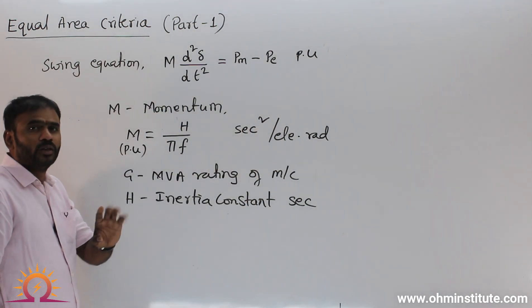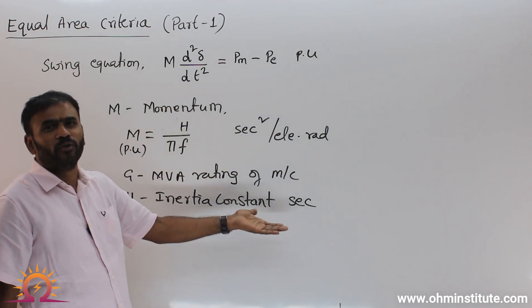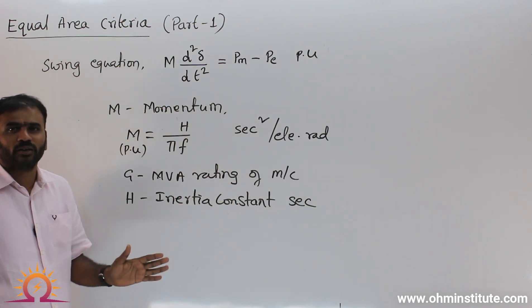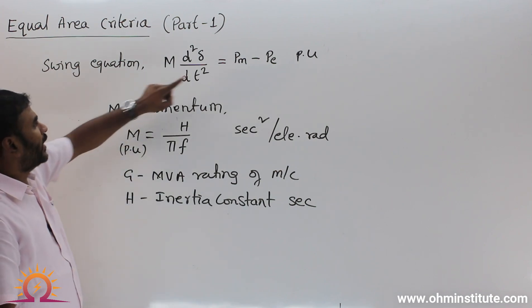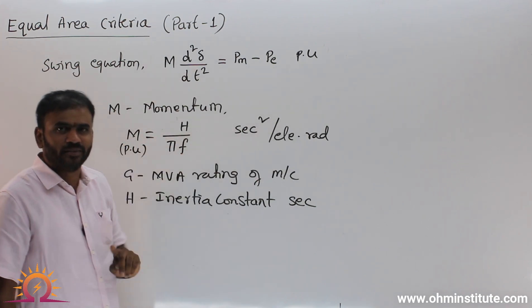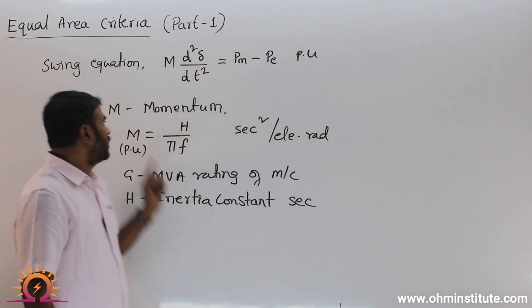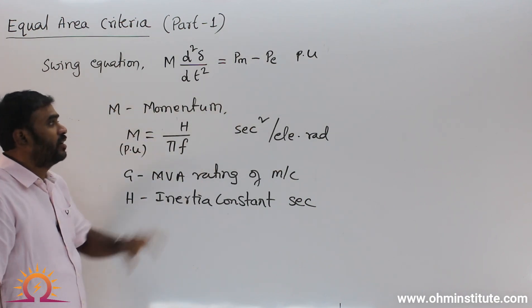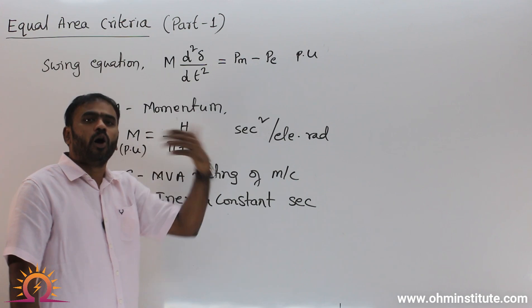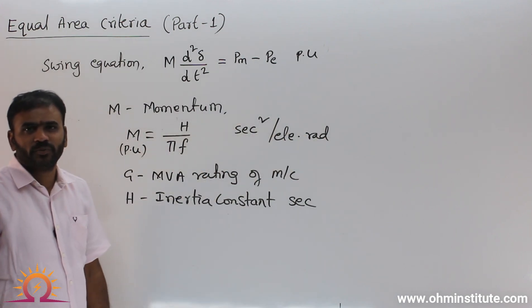In per unit form, the units of M become seconds squared per electrical radian — not mega joule-seconds. So be careful. The swing equation can be written in per unit form or in megawatt form. The only difference is: in per unit, M has units of seconds squared per electrical radian; in megawatt form, M has units of mega joule-seconds per electrical radian or megawatt-seconds squared per electrical radian.